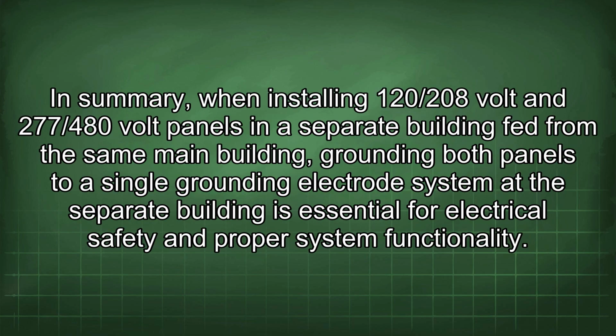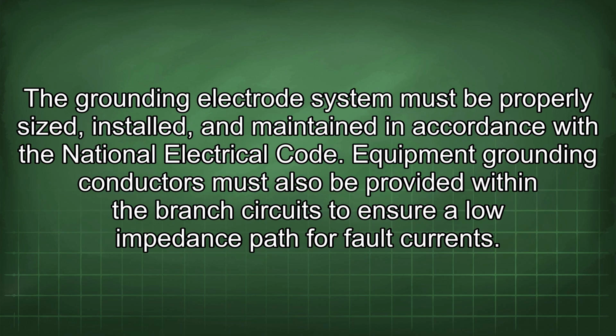In summary, when installing 120/208 volt and 277/480 volt panels in a separate building fed from the same main building, grounding both panels to a single grounding electrode system at the separate building is essential for electrical safety and proper system functionality. The grounding electrode system must be properly sized, installed, and maintained in accordance with the National Electrical Code. Equipment grounding conductors must also be provided within the branch circuits to ensure a low impedance path for fault currents.